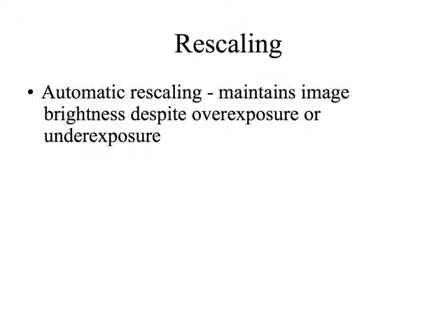And this is kind of where the really, really dirty stuff happens, if we're honest. This is where dose creep occurs, in rescaling. So the machine is going to automatically rescale for that data set based on a histogram model. So it can take a film that's way, way overexposed, compare those frequencies back to an appropriate exposure, and rescale it down to an appropriate exposure level, even if it's been overexposed or underexposed.